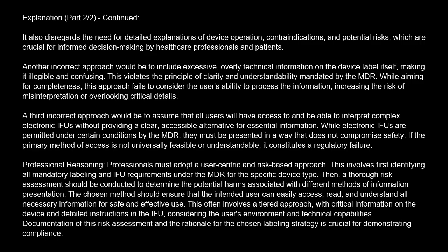This often involves a tiered approach, with critical information on the device and detailed instructions in the IFU, considering the user's environment and technical capabilities. Documentation of this risk assessment and the rationale for the chosen labeling strategy is crucial for demonstrating compliance.